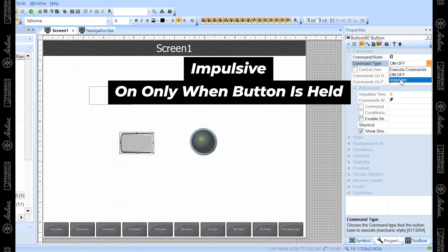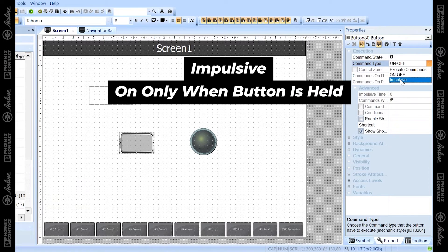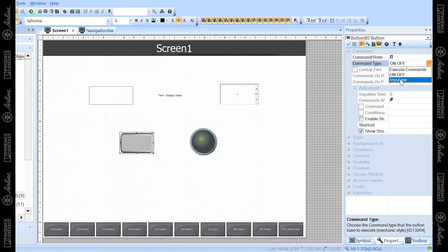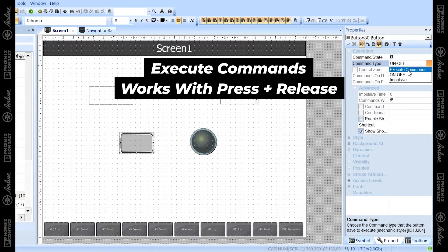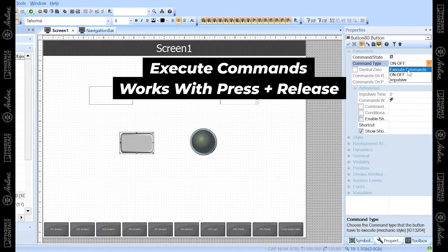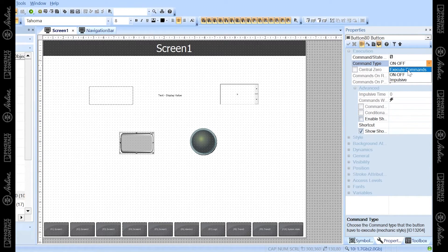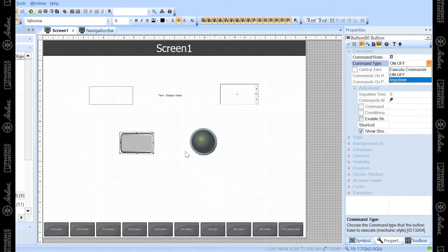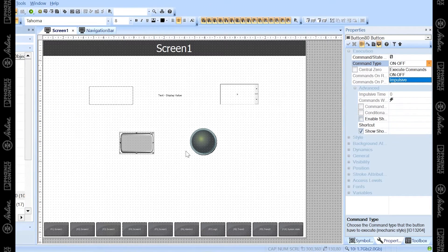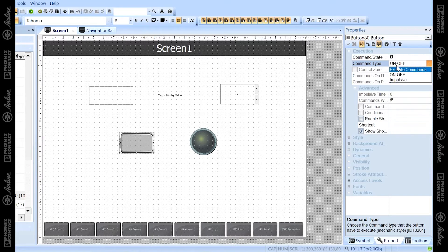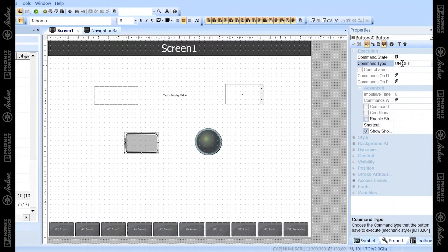'Impulsive' means the command or state variable associated with this button will be on only when the button is held. 'Execute commands' means launching a command either on the release or pressing of this button — for instance, setting a variable to a value, opening up another screen, or even changing the whole language of the screen if you're sending this HMI to another country. This is a very powerful aspect of button properties.